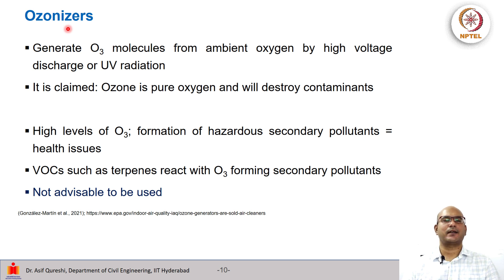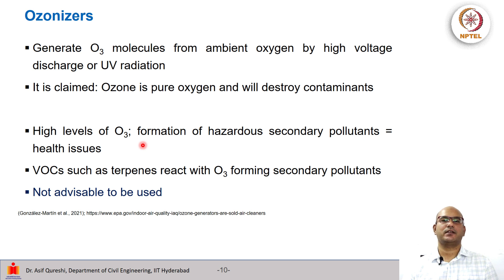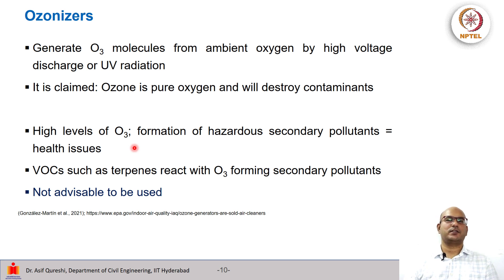Then we have ozonizers, which generate ozone molecules from ambient oxygen by high voltage discharge or UV radiation, and they claim that ozone is essentially pure oxygen and will destroy contaminants. However, the issue is that high levels of ozone can lead to the formation of hazardous secondary pollutants, resulting in health issues. Volatile organic compounds such as terpenes can react with ozone to form secondary pollutants. In general, it is not advisable to use ozonizers due to potential chemical reactions and health impacts from higher ozone levels indoors.